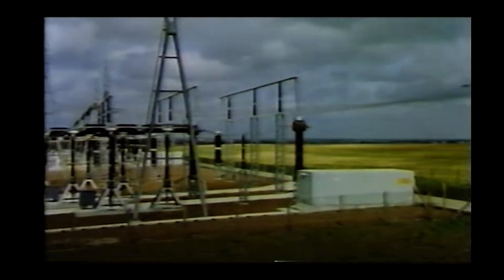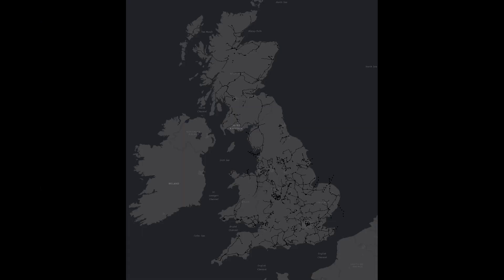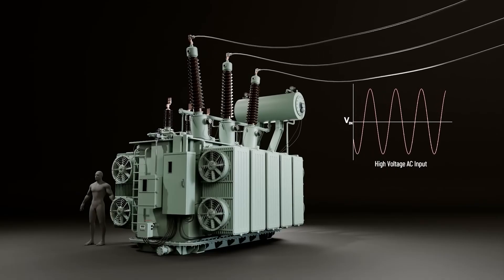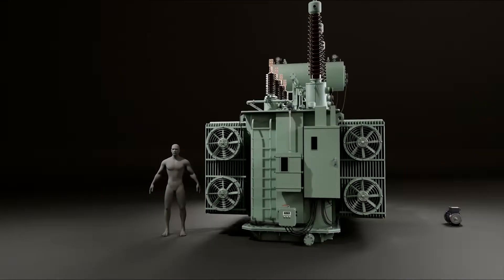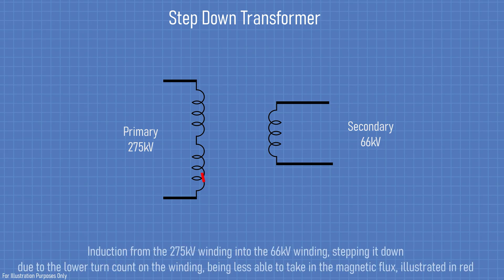But how did they actually get the power? Transmission substations operate at 132, 275, or 400 kV in the UK. Inside a substation, a supergrid transformer, or SGT, steps that voltage down to distribution levels — usually 33, 66, or 132 kV. For example, you might have a primary winding at 275 kV and a secondary winding at 66 kV.